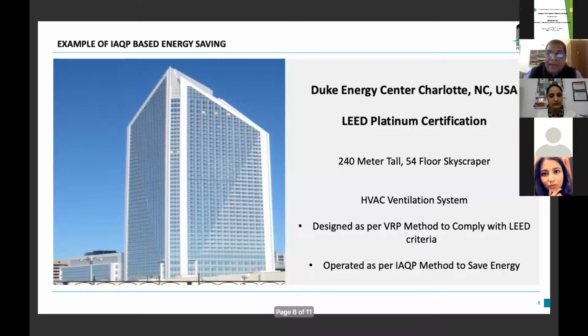be adopted. Now there was a problem. The LEED green building code at that time did not have a provision for the IAQP method. They were only accepting the VRP method. So they were not ready to certify it as LEED Platinum. So the consultant designed the building based on the VRP method, the ventilation rate procedure method, and once it was certified, they also did the calculation based on the IAQP method, where less outdoor air is required and better indoor air quality can be provided to save energy. So this is one case of a hybrid method where it predominantly runs on IAQP-based energy saving.